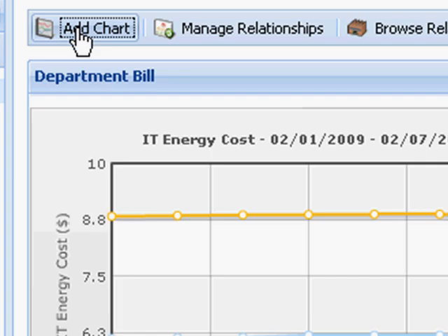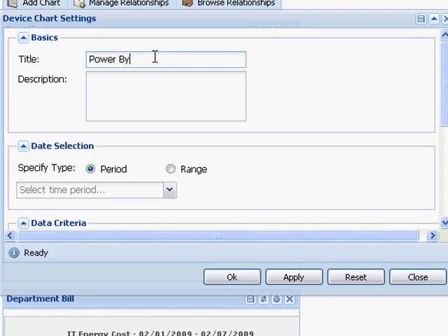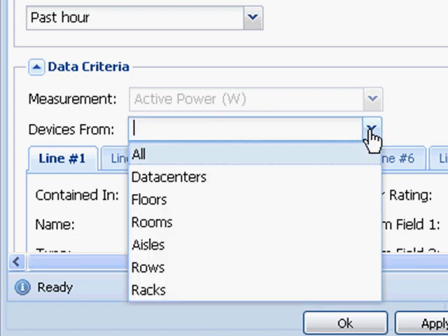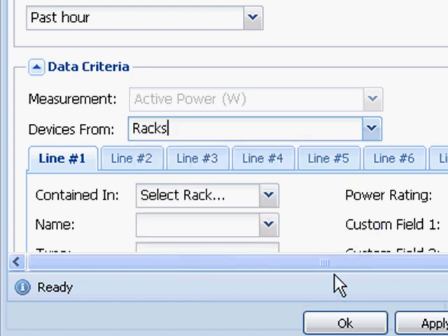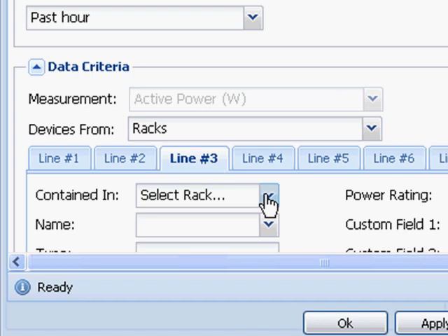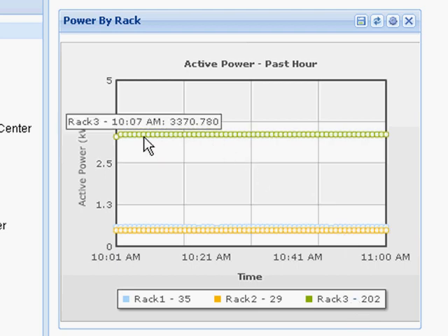I'm going to create another chart to show power by rack. I want to do my power by rack for the past hour. Past hour and last hour, by default, will only allow you to graph active power in watts, so that's selected as is. This time I'm going to show you the power of the containment field — I'm going to say I'm graphing racks, which makes it easy to use my containment field and select my racks. Line one I'll make rack one, line two rack two, line three rack three. I can enter an additional rack for each line, but I'll cut it off there and click OK. This shows you how you can graph multiple racks on one chart.